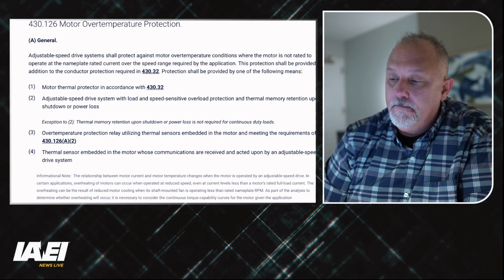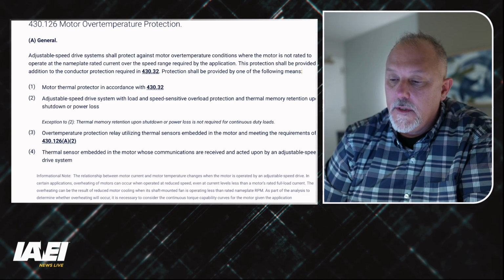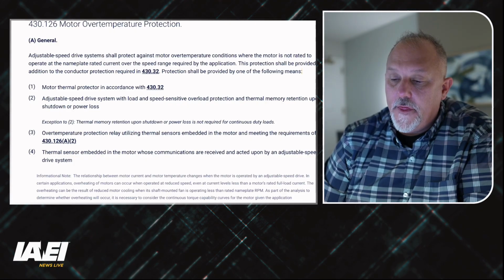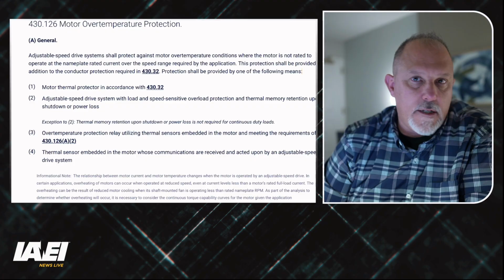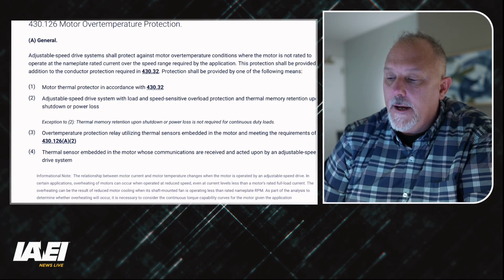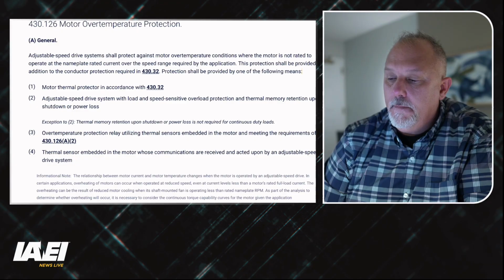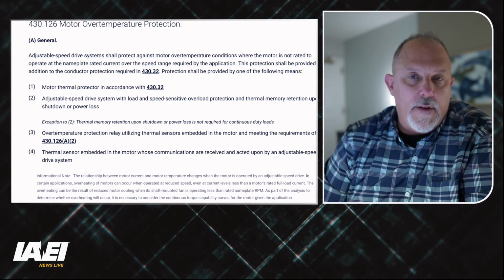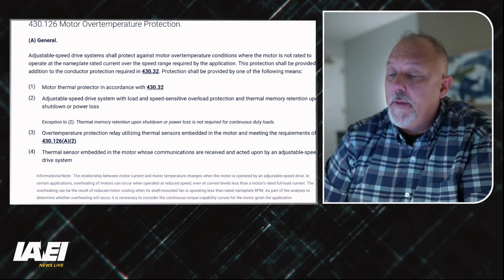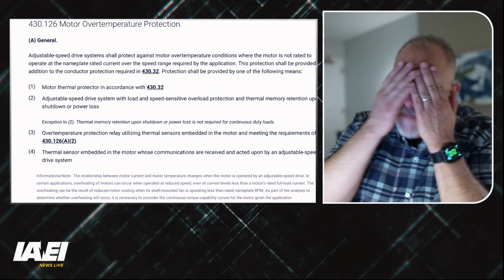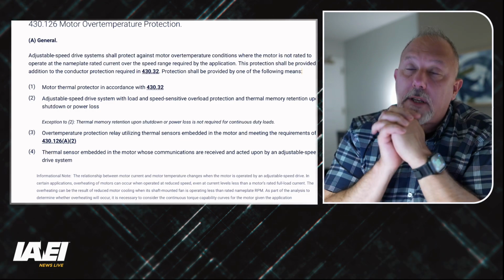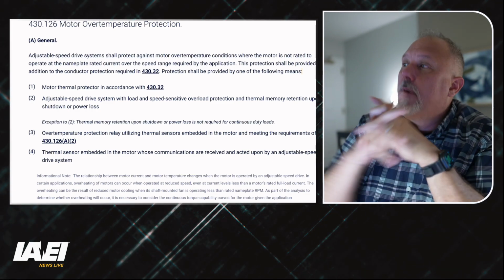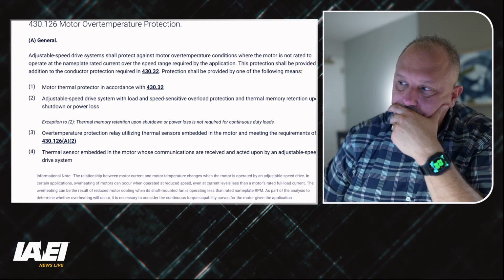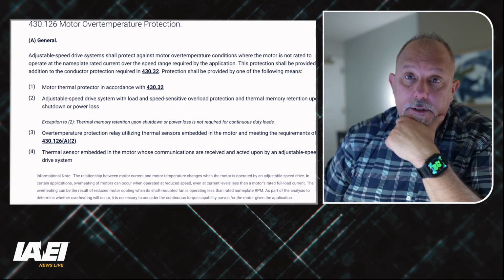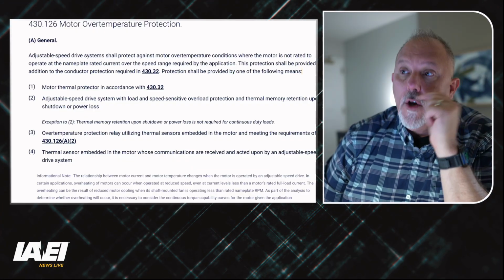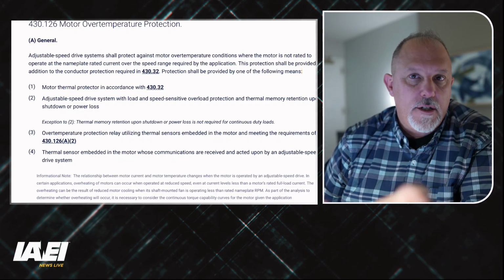You've got motor thermal protection. You could have RTDs installed inside the motor, things like that. You may have a device or a piece of equipment that has thermal memory. What thermal memory means is it tries to replicate the cool down of the motor. Remember, if I do multiple starts, it's going to know that you tried starting this thing multiple times. Every time you do that, you're building up heat in the motor, which changes the damage curves.